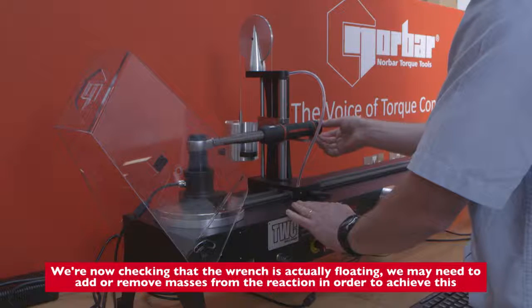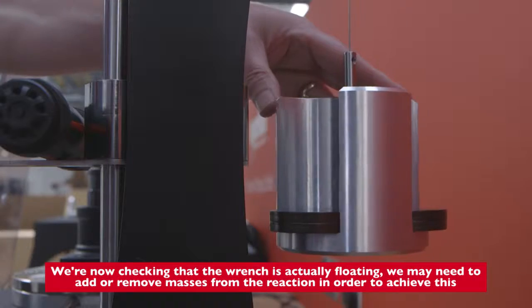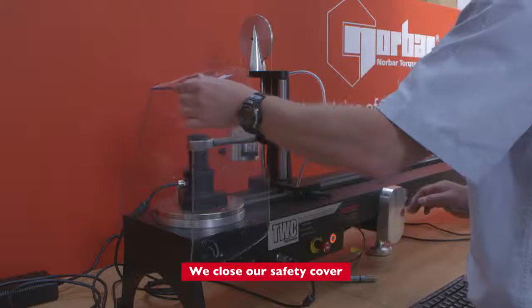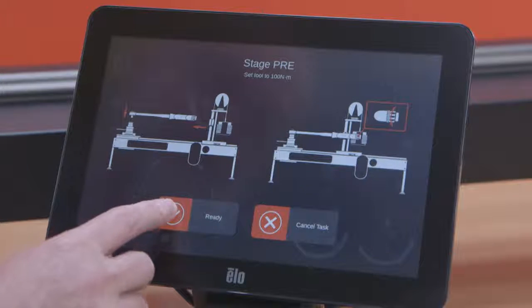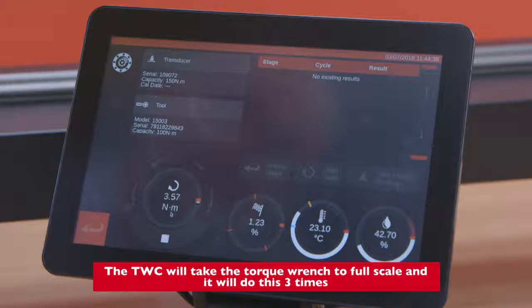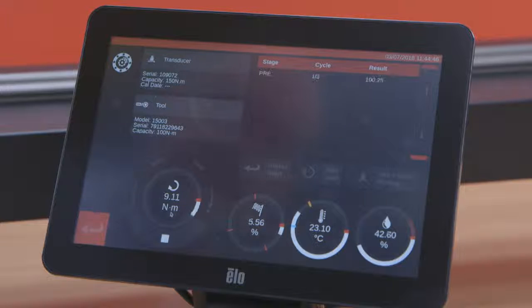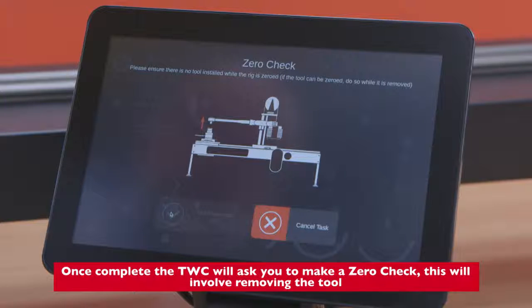We're now checking that the wrench is actually floating. We may need to add or remove masses from the reaction in order to achieve this. We close our safety cover. The TWC will take the torque wrench to full scale, and it will do this 3 times. Once complete, the TWC will ask you to make a zero check. This will involve removing the tool.